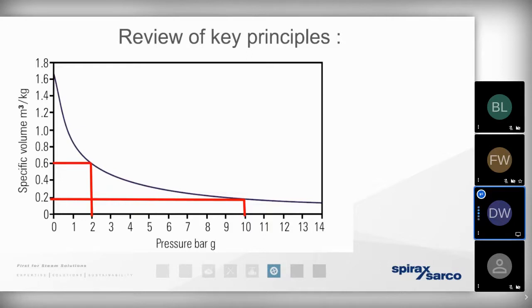So if we get a fall in pressure of the condensate, then we know that any sudden fall in pressure is likely to result in that flash steam being generated. And as that flash steam is generated, we're going to see a sudden expansion as a result of the phase change. And that's why that flash steam is so often vented to atmosphere. That's indicative of an energy loss.